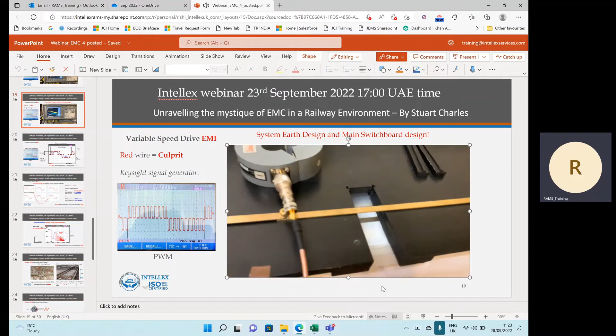Now we could find, if we disconnect the current probe, which I'll do shortly, that the trace stays much as it is. In other words, we're at the system noise floor. Let's do that to see if in fact we do have any external current. The probe will hopefully come off - always difficult when you're doing live videos. There we go, so we're not measuring any current now, but have we got the same reading? We have indeed, let's max hold that and view it. So basically we're measuring noise floor of the receiver. We cannot see any external contamination of current when we're using a screened cable.